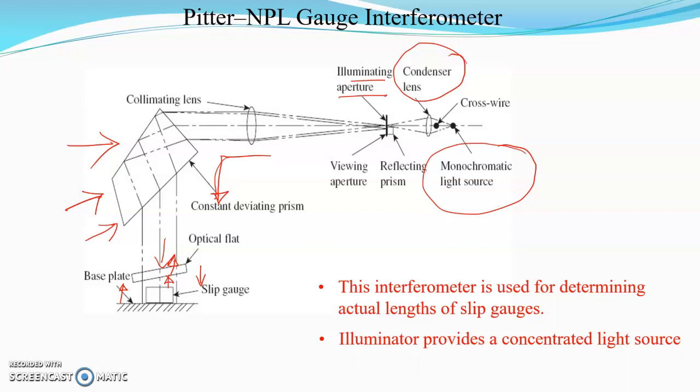These three rays combine to form different patterns and are redirected through the optical system again. The path is slightly deviated because of the taper or angle of the optical flat. The light is then incident on the viewing aperture, and the fringe pattern appears there.